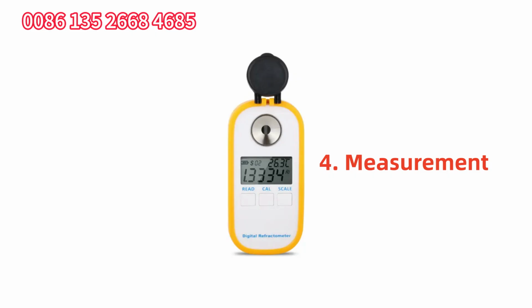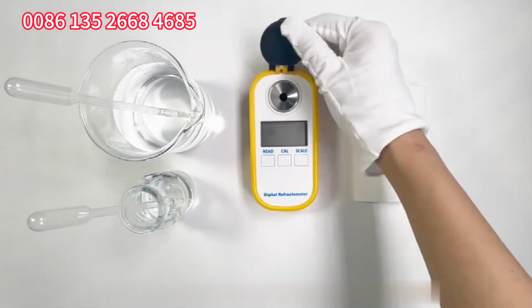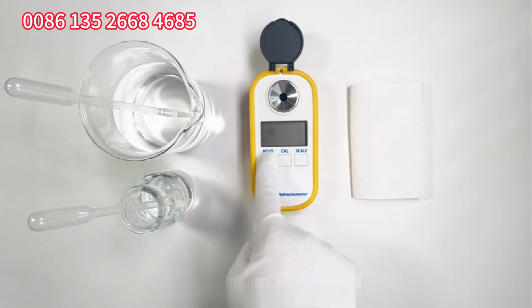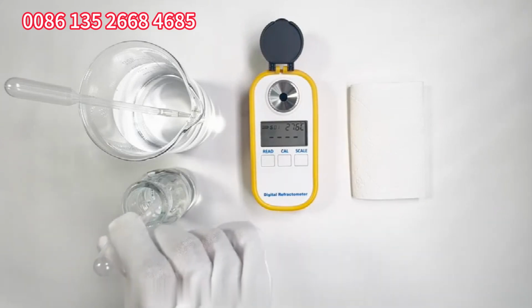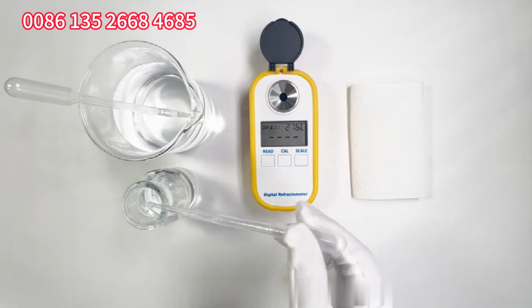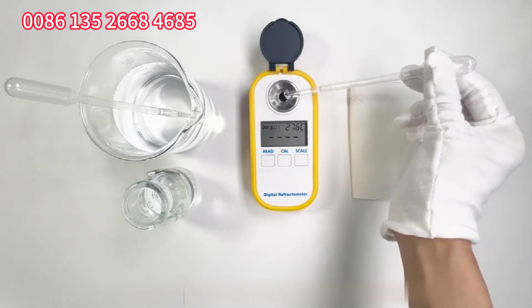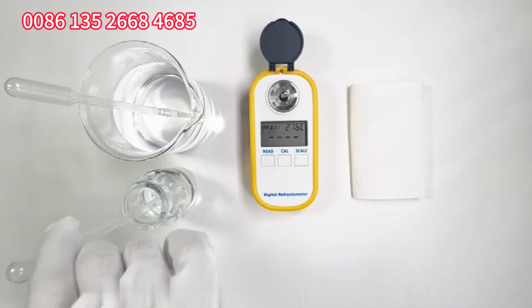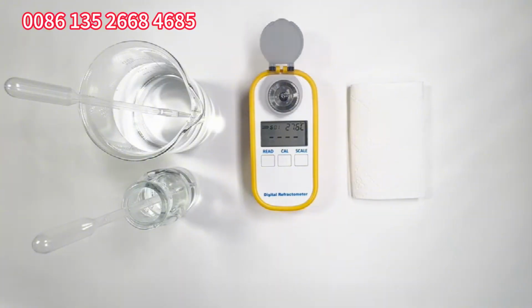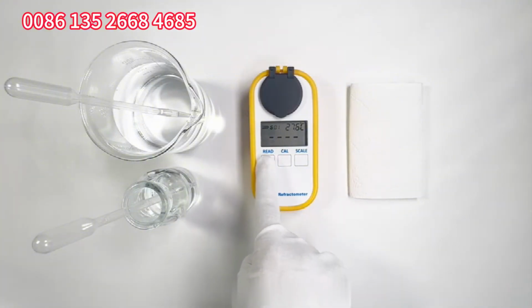Step 4. Measurement. Open the shield and press the read button to start. Drip 0.2 to 0.3 milliliters of your sample onto the prism. For accurate results, use the pipette to break any small air bubbles in the liquid. Close the shield. Press the read button once for a single measurement.